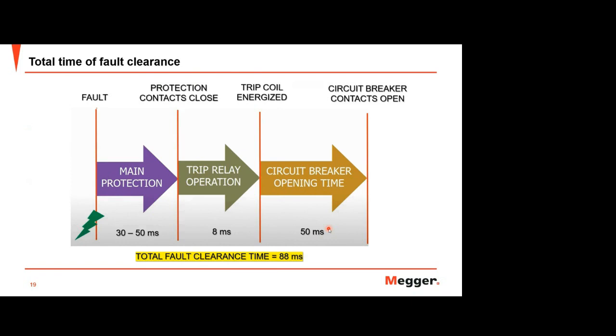So with this condition, we can say this total fault clearance time is still okay for systems up to 500 kV. But remember, this leaves just around 12 milliseconds remaining. So if either the relay or the circuit breaker fails, this can add to the total clearance time. But based on many experiences, I can say the failure of the relay contact has a very low chance compared to the circuit breaker opening time. So this is why first trip is more effective to analyze your clearance time.